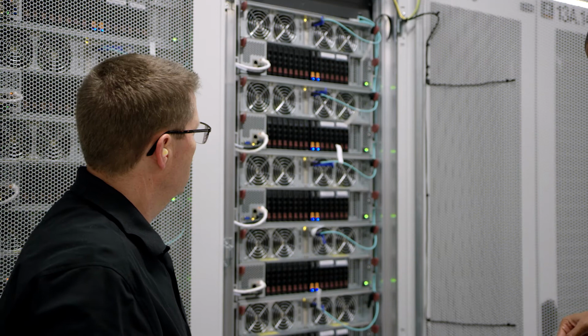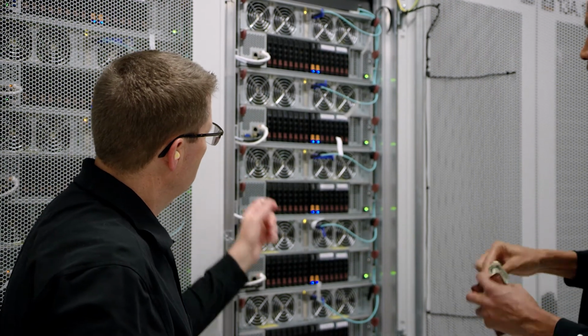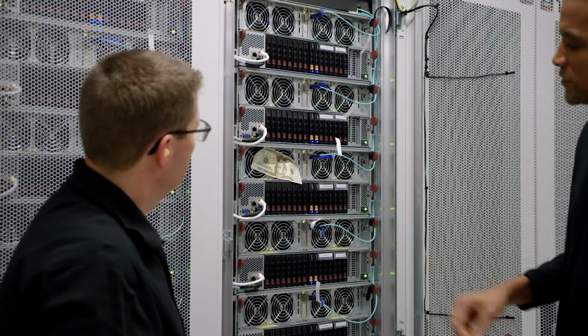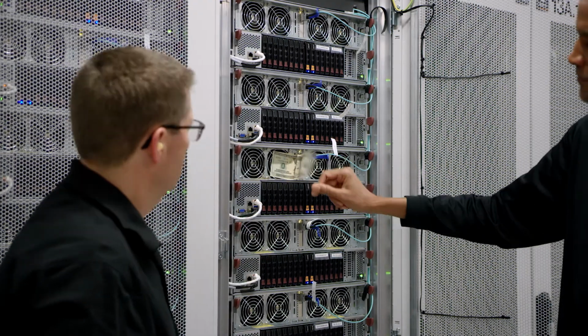One of the other things, because this is something that's really important for us, and this is something that we really find ourselves talking to customers about all the time. One of the tricks that we do is that we just have a dollar bill, and we turn on the server, we turn on the switch, we put the dollar bill in front of the fans. If it sucks, we know which direction it is. Because quite often, if you just put your hand, it's very difficult to tell.